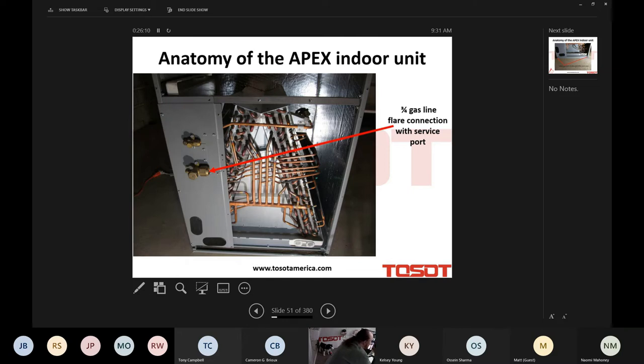I love this. So again, a great benefit to have service valves, not only at the outdoor unit, they're there too, right? Like any traditional system, but to have them at the indoor unit as well, a great advantage. And we'll talk more about that when I get into evacuation and leak testing and charging. You'll see exactly what I'm talking about. But let me go back just for a second.